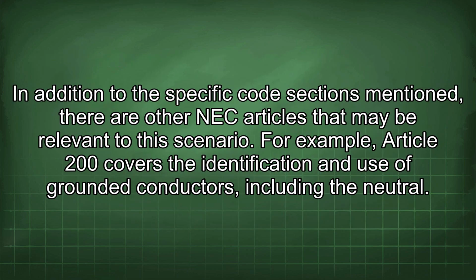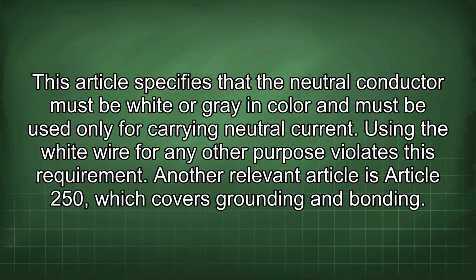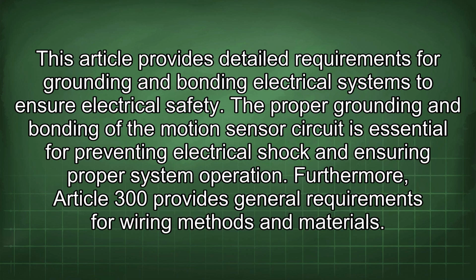In addition to the specific code sections mentioned, there are other NEC articles that may be relevant to the scenario. For example, Article 200 covers the identification and use of grounded conductors, including the neutral. This article specifies that the neutral conductor must be white or gray in color and must be used only for carrying neutral current. Using the white wire for any other purpose violates this requirement. Another relevant article is Article 250, which covers grounding and bonding. This article provides detailed requirements for grounding and bonding electrical systems to ensure electrical safety. The proper grounding and bonding of the motion sensor circuit is essential for preventing electrical shock and ensuring proper system operation.